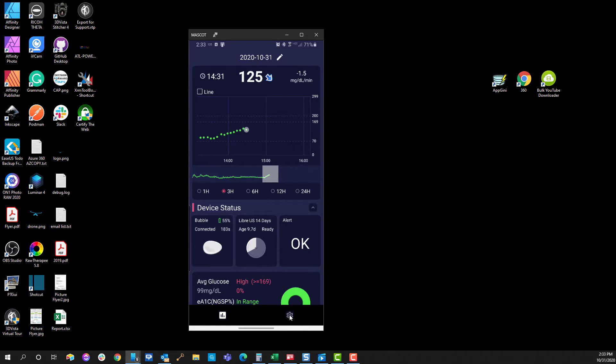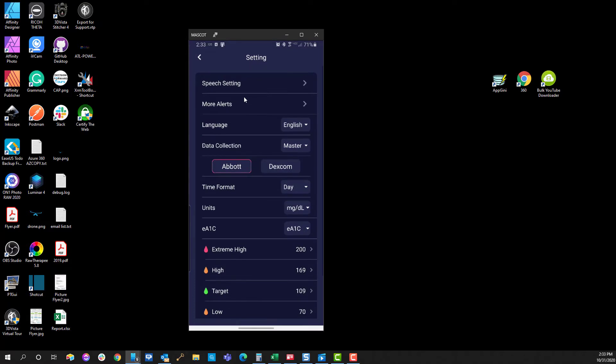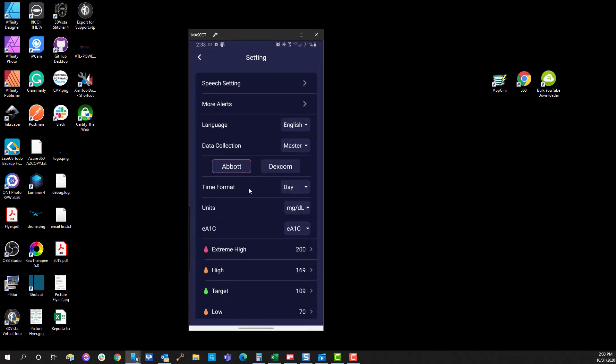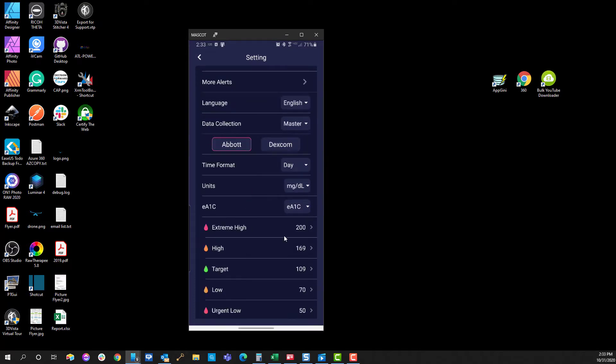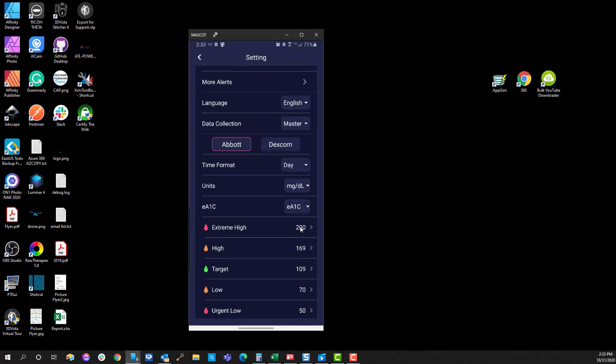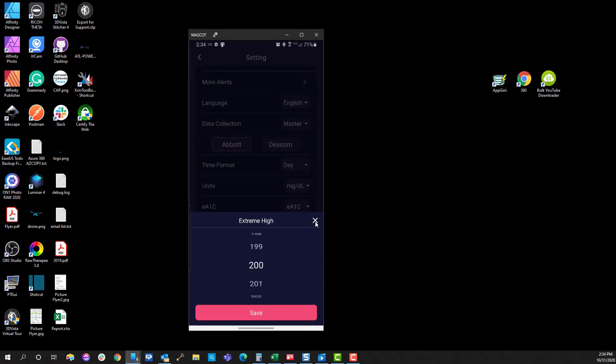The next thing you're going to want to do is come over to the settings and cogs area. We're going to go down through some of these and make sure that these are what you consider to be correct. These are the default settings: an extreme high of anything over 200. For you that may be 300 or 260 or 250 or whatever it may be. You can just click into it, make the changes, and then press save at the bottom. These are the default settings so I'm going to leave them because personally they work for me.